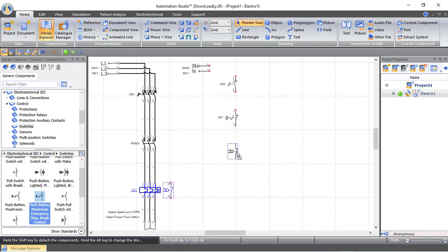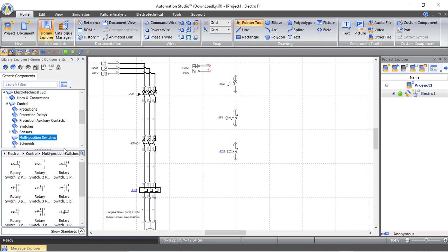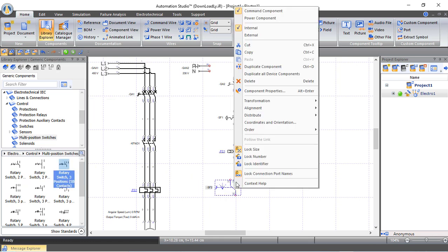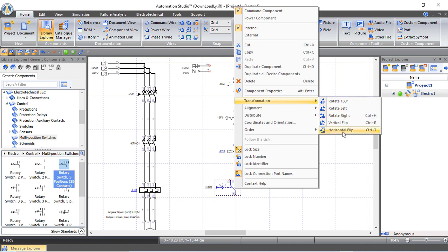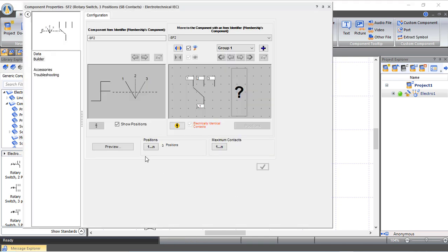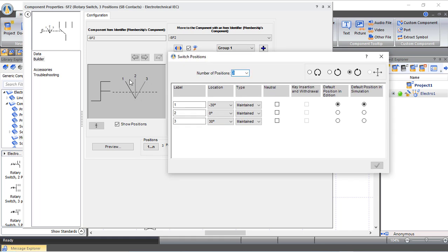We drag and drop the thermal overload contact. Now from multi-position switches we select a three-position rotary switch to choose between continuous mode and jogging mode. We right-click it and apply a horizontal flip, then double-click to configure its positions: position 0 is the off position, position 1 is jogging, and position 2 is for continuous operation.